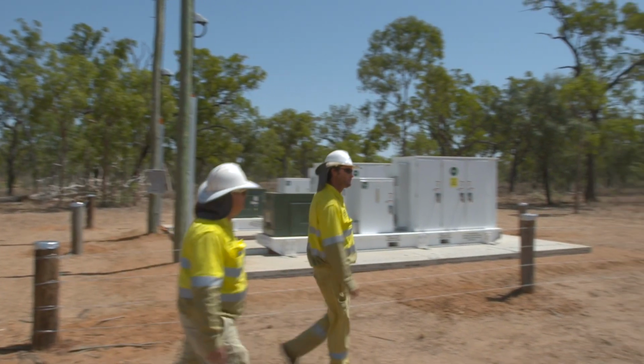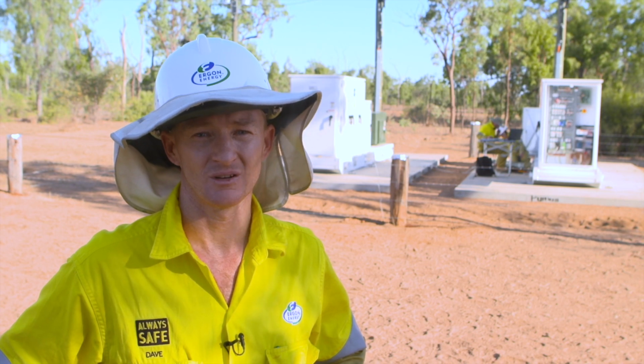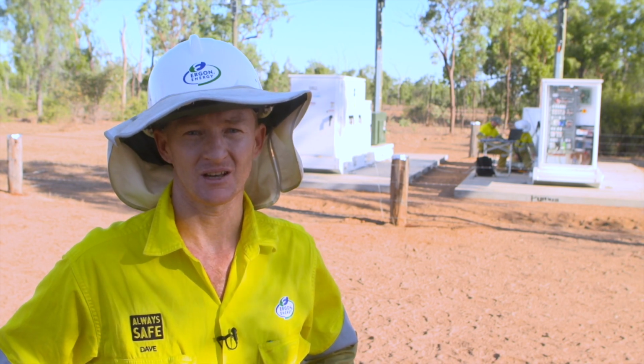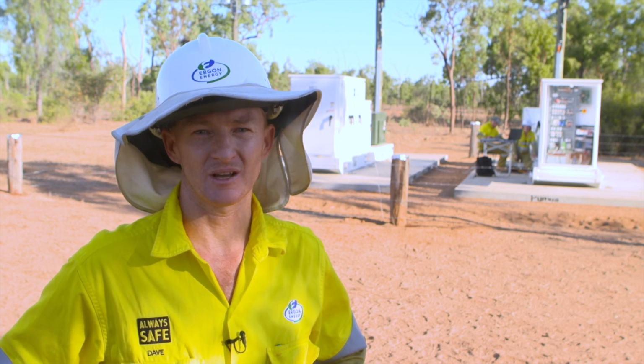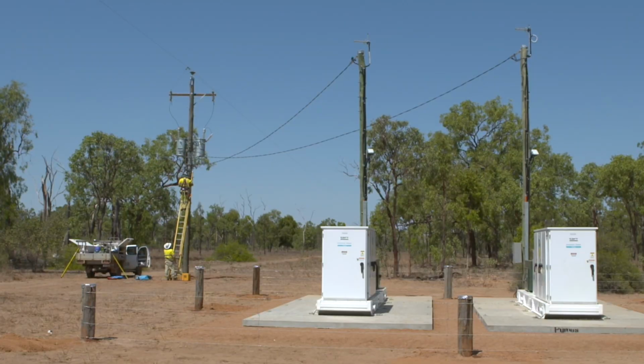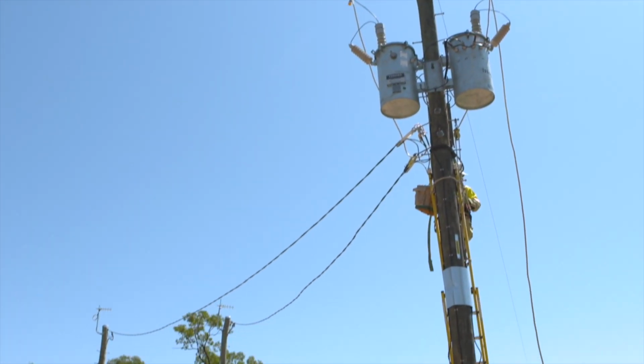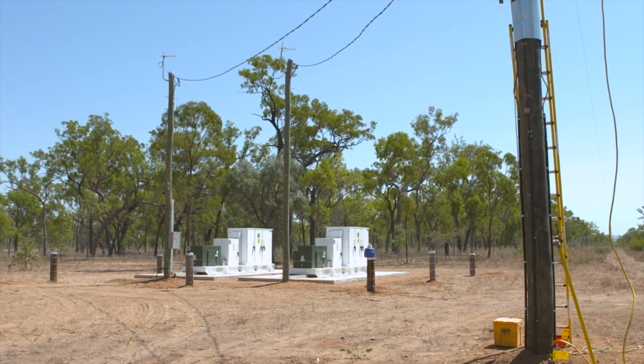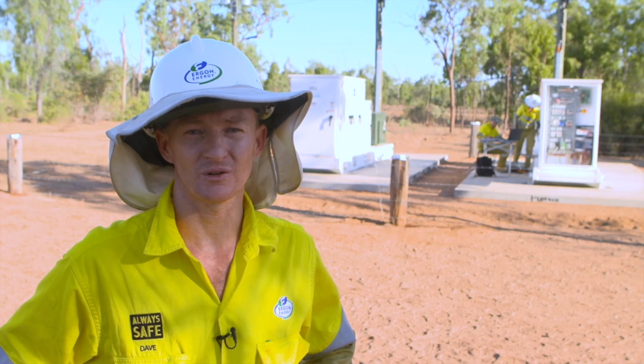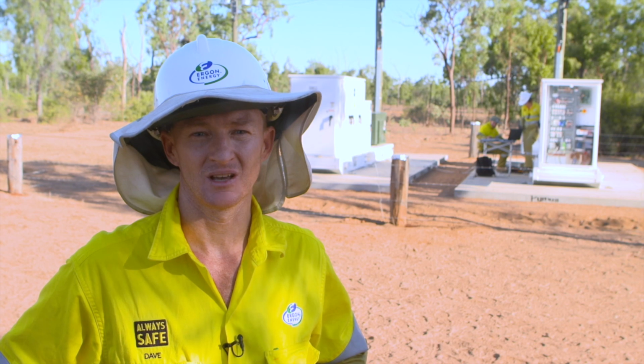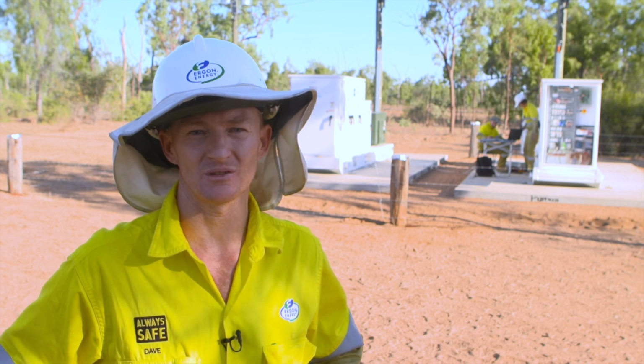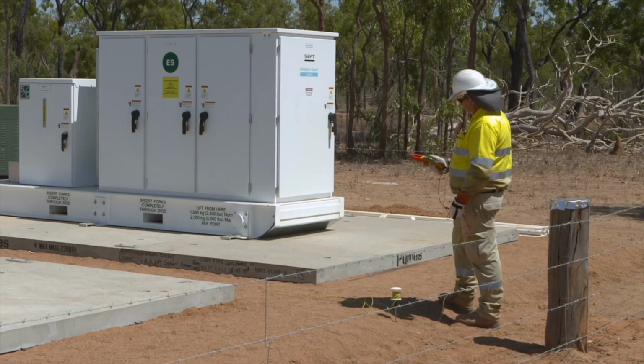If there is a distribution defect such as a leaking transformer or broken HV insulator, then HV isolation and access will be required as per the P53 process. If there is a GUSS defect, then LV isolation at the distribution substation and the DC circuit breakers is sufficient. If the defect is minor or there is a suspected fault within the GUSS, a voltmeter with a trailing lead shall be used to determine that the metalwork is not live.